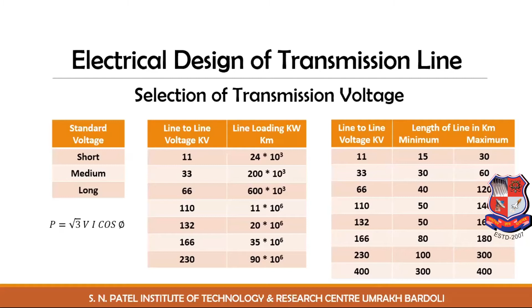Depending upon the length of the transmission line, the line voltage is also selected, which is shown in table 3. Here line-to-line voltages are given like 11 kV, 33 kV, 66 kV. For all the voltages, there is a minimum and maximum range for the length of the line. For example, for 11 kV line, the length is between 15 to 30 km. For 33 kV, it is 30 km to 60 km. For 66 kV, it is 40 to 120 km. Similarly we move further to 110, 132, 166, 230, and lastly for 400 kV, the length of the line is 300 to 400 km.